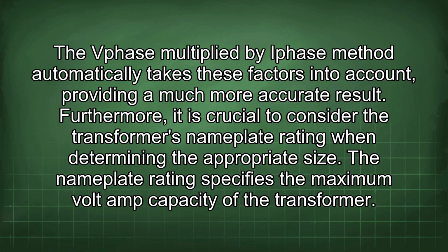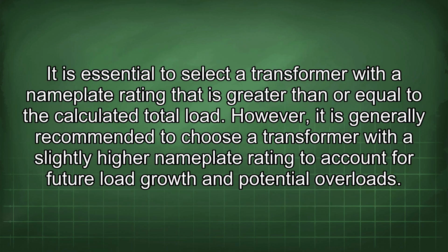Furthermore, it is crucial to consider the transformer's nameplate rating when determining the appropriate size. The nameplate rating specifies the maximum volt-amp capacity of the transformer. It is essential to select a transformer with a nameplate rating that is greater than or equal to the calculated total load. However, it is generally recommended to choose a transformer with a slightly higher nameplate rating to account for future load growth and potential overloads.